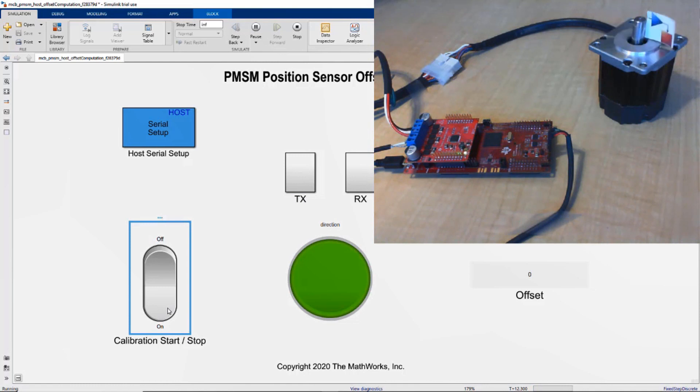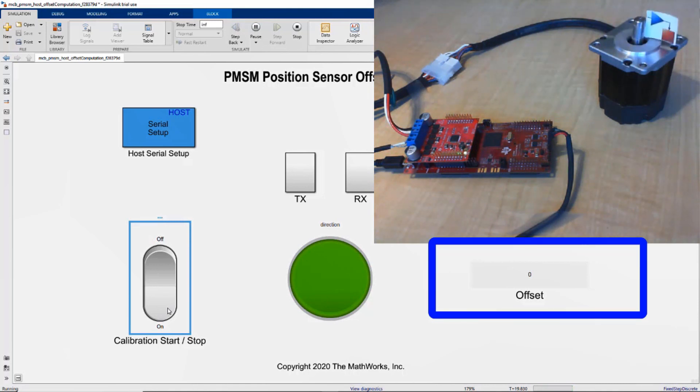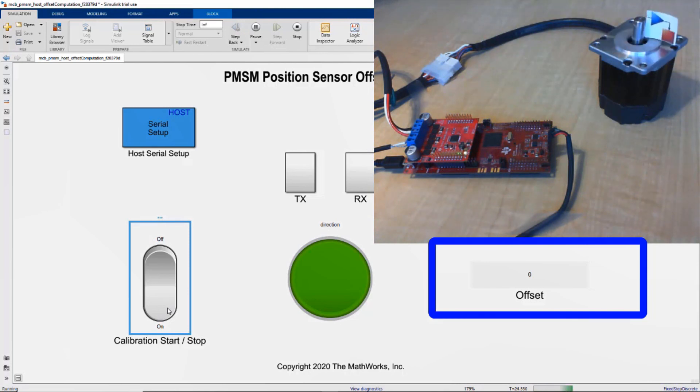Now the green LED here shows the motor is spinning in the right direction, which is counterclockwise. If not, the motor spins in clockwise direction. The LED turns red, indicating we need to swap the wires between the motor and the inverter.